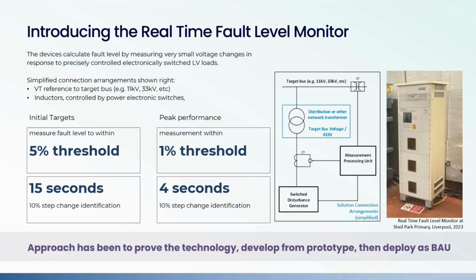And the device, when it's switched on, will then switch the LV inductors, the LV inductive load, multiple times a second using the power electronic switches. What that does is create a fairly sizable voltage response at LV, which, just to note, if the LV distribution board is also supplying customers, there are things we can do to configure it to make sure that we stay well within P28 flicker limits. But it creates a reasonable voltage response at LV, which can then be seen as a very, very small voltage response at the higher voltage via the VT.